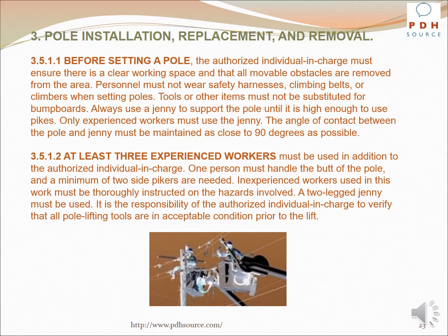At least 3 experienced workers must be used in addition to the authorized individual in charge. 1 person must handle the butt of the pole and a minimum of 2 side pikers are needed. Inexperienced workers used in this work must be thoroughly instructed on the hazards involved. A 2-legged jenny must be used. It is the responsibility of the authorized individual in charge to verify that all pole lifting tools are in acceptable condition prior to the lift.